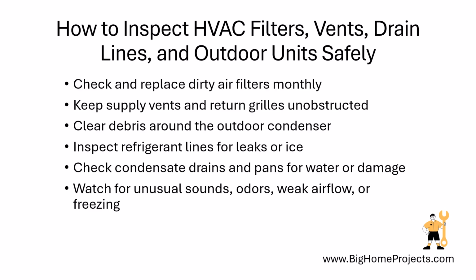Outside, turn off power before removing leaves, grass, and debris from around the condenser, and keep several feet of open space around it. Check the refrigerant lines for damaged insulation, oily spots, or ice, since those signs can point to a leak that requires a trained technician.